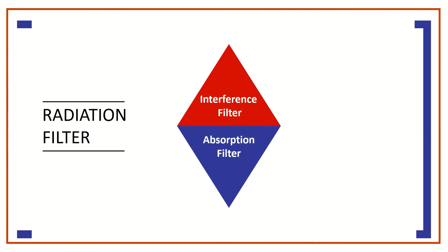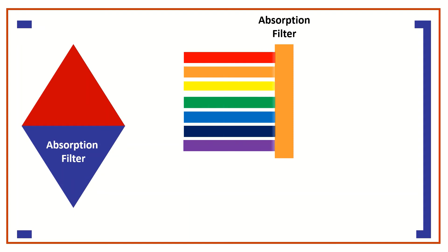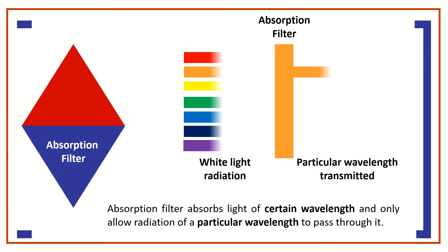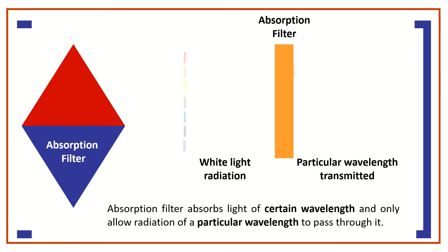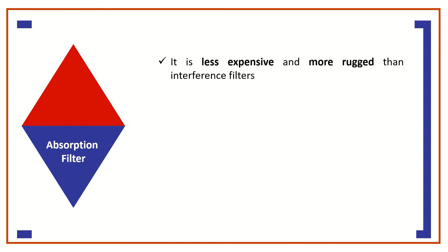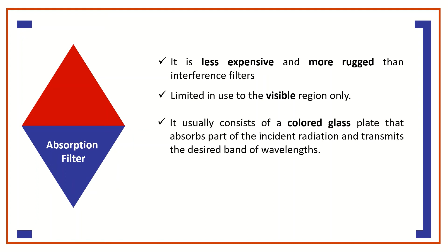Absorption filters absorb light of certain wavelengths and only allow radiation of a particular wavelength to pass through. This type of filter is generally less expensive and more rugged than interference filters, and is limited in use to the visible region. It usually consists of a colored glass plate that absorbs part of the incident radiation and transmits the desired band of wavelengths.